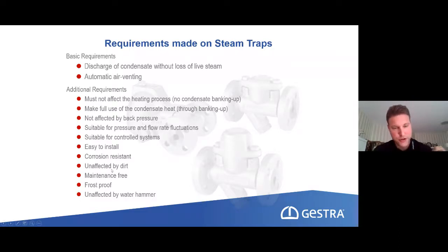Being unaffected by dirt is also very important. Dirt is in almost each and every steam system. This could be, let's say, grease or little pieces of paper, if we have a paper mill where we want to heat up the machine to create our paper. Or we could go to a steel mill. If we create steel, we could have even little steel balls in our pipeline which travel through the system, and of course you can imagine if a little steel ball is blocking such a steam trap, this is not fine. So some steam traps can handle dirt very well and some don't. We will see how that works. Frost-proof is also a nice thing to have, but it depends on the ambient conditions and where we are located on the planet.